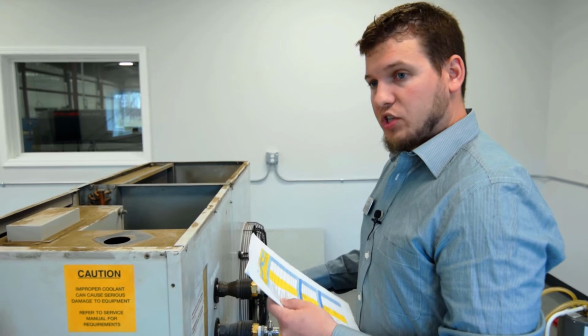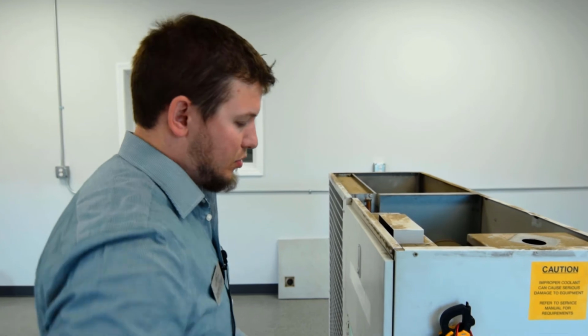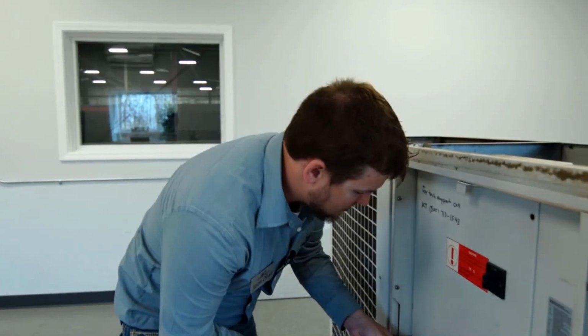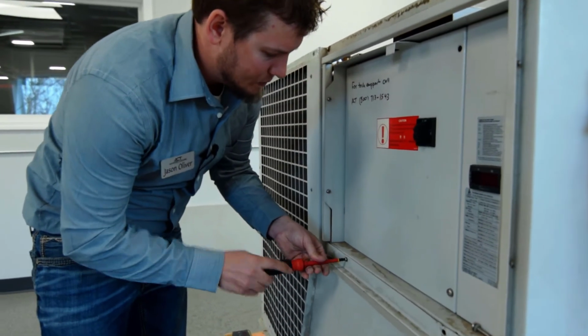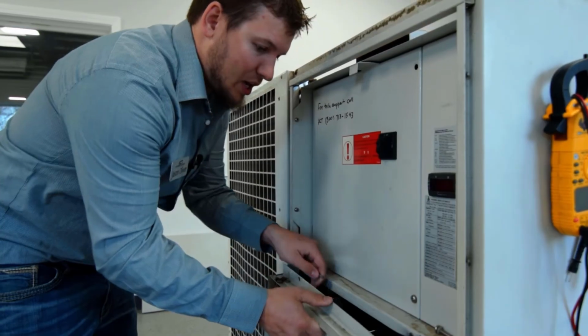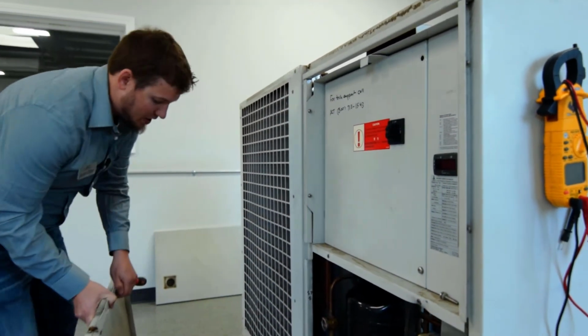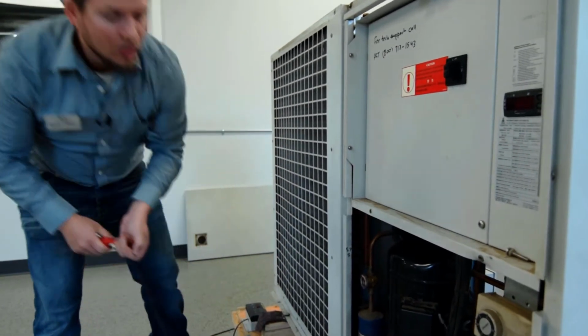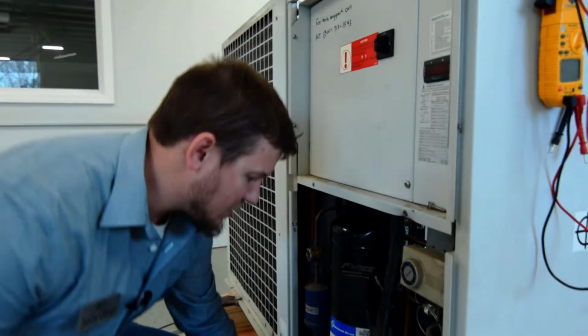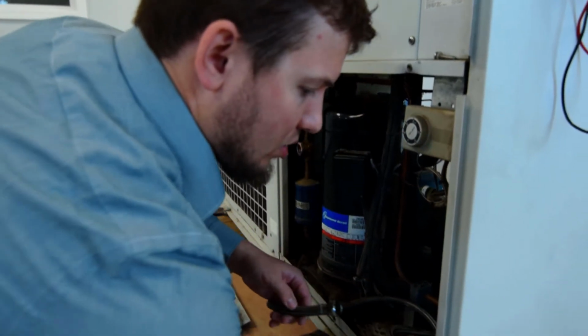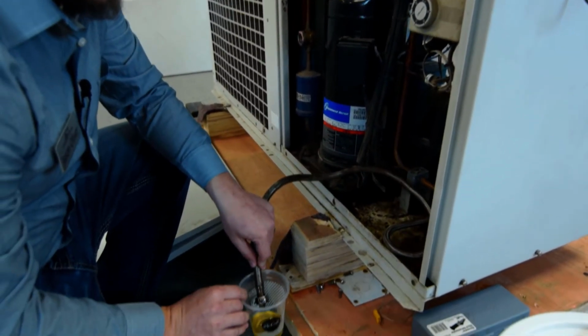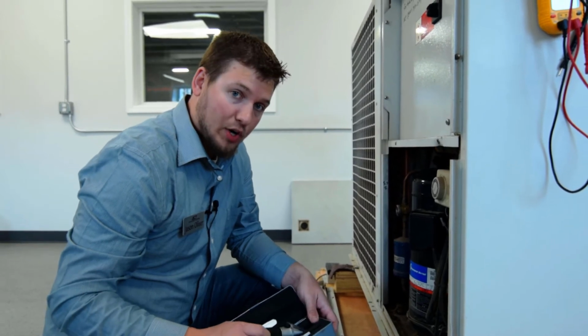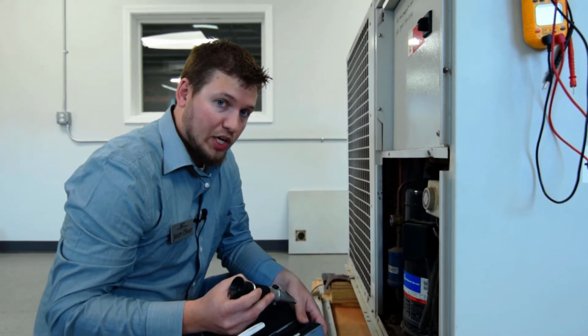Step number 23 on this checklist is to verify that the glycol in the system is at a 50% propylene glycol rate. The best way to do this is to remove this front cover. Most of the time there's screws on the bottom and 2 on the top. Once you remove the cover though, you can access this stainless steel flex line here. And all you have to do is crack open the drain valve and you can fill up a cup to get your sample. Once you have your sample, the best way to verify you have a 50% propylene glycol mix is to use a refractometer. You can pick these up at any local HVAC supply house.